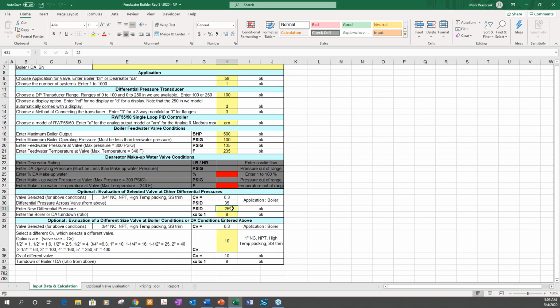And what it will do is check to see if we have only a 25-pound differential, whether the 3/4 inch valve will be able to meet the demand. The second option is, based on the above conditions, instead of a 3/4 inch, say we want to use a 1 inch valve. Well, we have to look up the CV value. They provide a nice chart here for you, and you see that a 1 inch valve has a CV of 10. So in that case, we input 10 in here.